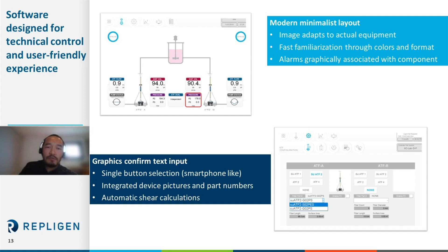The top menu on this interface is always visible, while submenu items appear for more detailed setup and configuration. Note that here you can see a lot of different ATF devices and part numbers. These are all automatically built in, programmed into the controller, and it also includes more specifications for that device that you've chosen. And just a few additional points about the software. The HMI and security features can be configured to suit your needs, such as units, date and time formats, log out and restart settings. The actual operating system is based on Windows, so you have Windows level security with pre-programmed default users, ability to set username and passwords to internal requirements, and access levels are assigned by Windows level users.